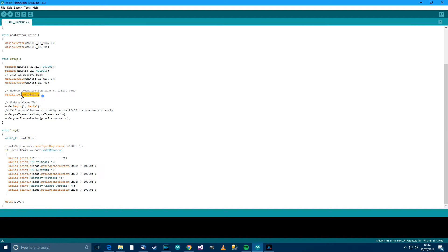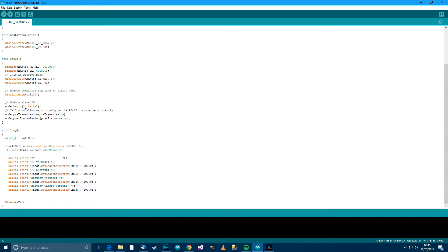Then we're setting Serial Communication at 115200 Baud, which is what I usually use anyway, so there's no problem. Mod Bus Master Slave ID 1. In the documentation that you use, it should say the ID of the slave.